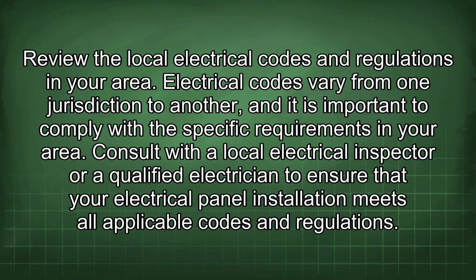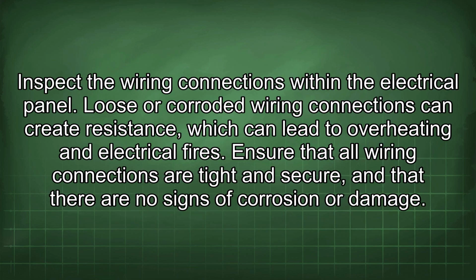Inspect the wiring connections within the electrical panel. Loose or corroded wiring connections can create resistance, which can lead to overheating and electrical fires. Ensure that all wiring connections are tight and secure and that there are no signs of corrosion or damage.